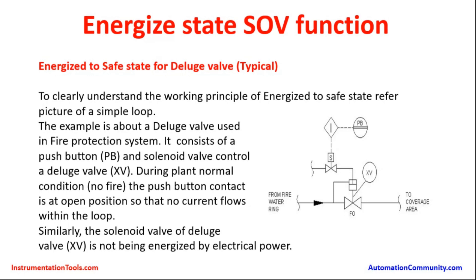Here we are seeing a typical example of a Deluge valve used in a fire protection system. To clearly understand the working principle of Energize to Safe State, refer to the picture of a simple loop. The example is about a Deluge valve used in a fire protection system. It consists of a push button and a solenoid valve controlling a Deluge valve.